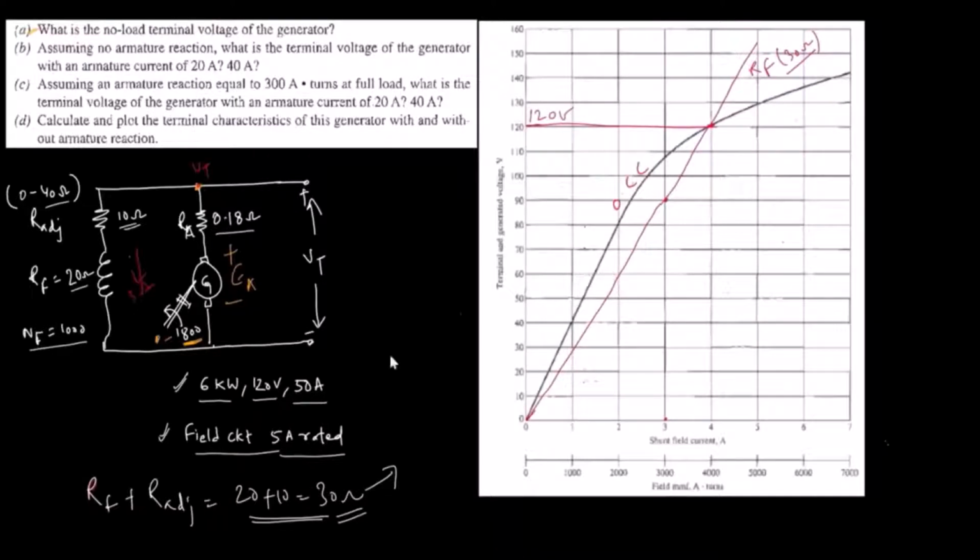Why is the intersection of these two lines the no load? In self-excited generators, due to residual flux, the voltage builds up to a no load voltage as the speed increases from 0 to rated speed. And this buildup takes place due to the difference between the OCC and the RF line. Due to this only it will build up. If the RF line is just touching or above the OCC, then voltage buildup will not take place.